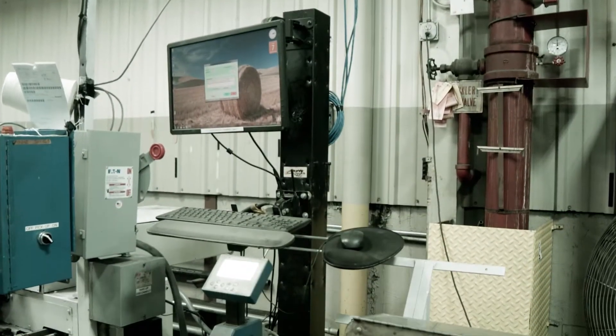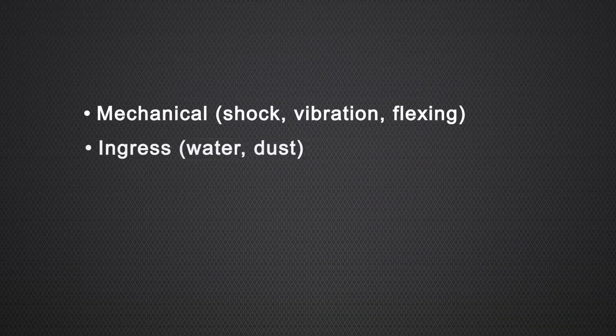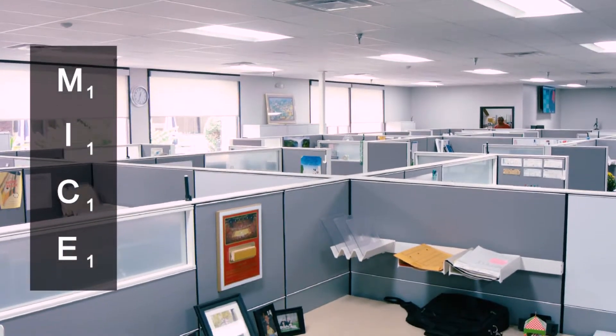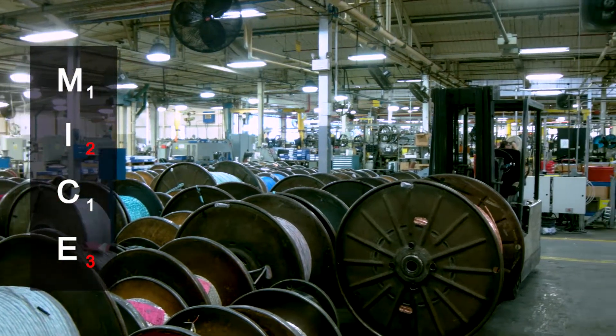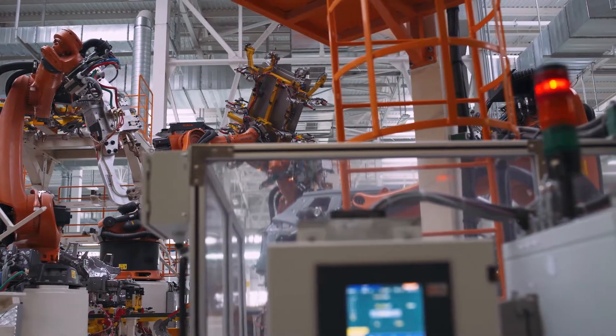Here you have to think about MICE — no, not that kind of mice. Instead, we are talking about an environmental rating system. You assess the true operating conditions and assign a value of one to three for specific factors. At the lower end of the spectrum are office-like conditions. Rate any one of the factors at two or higher and you need industrial cable. Ordinary commercial grade cables are just not built to withstand these harsh conditions.